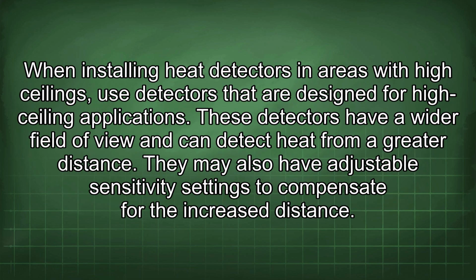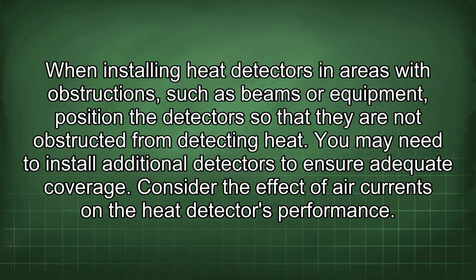When installing heat detectors in areas with high ceilings, use detectors that are designed for high ceiling applications. These detectors have a wider field of view and can detect heat from a greater distance. They may also have adjustable sensitivity settings to compensate for the increased distance. When installing heat detectors in areas with obstructions, such as beams or equipment, position the detectors so that they are not obstructed from detecting heat. You may need to install additional detectors to ensure adequate coverage.